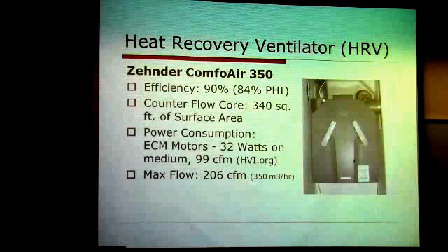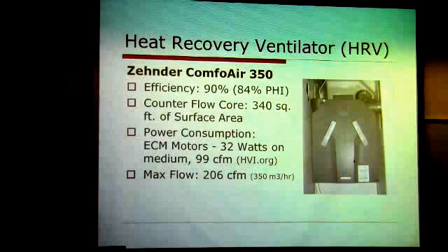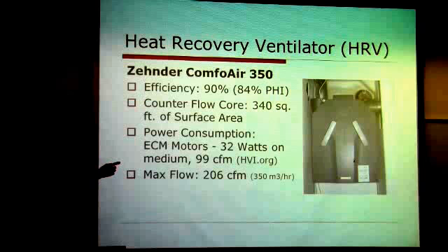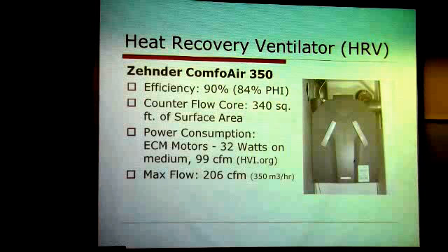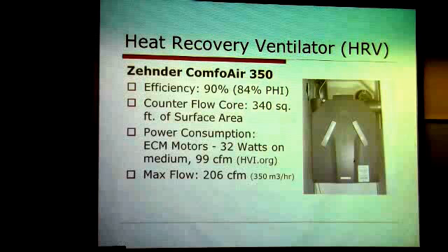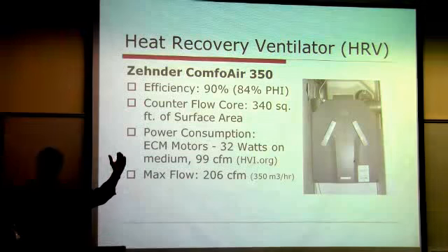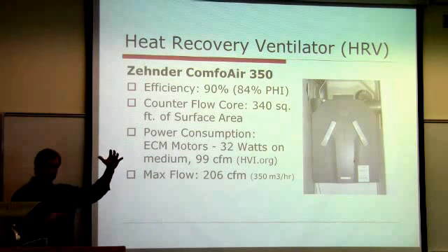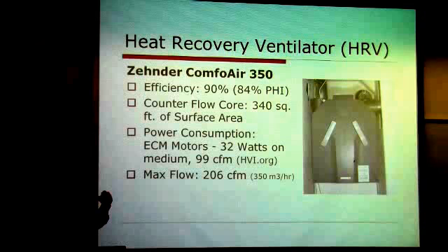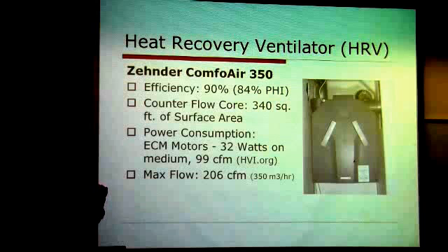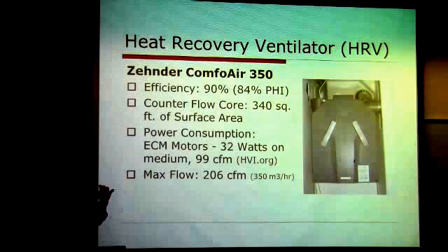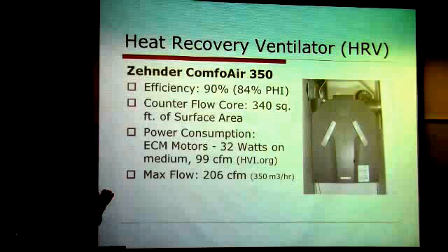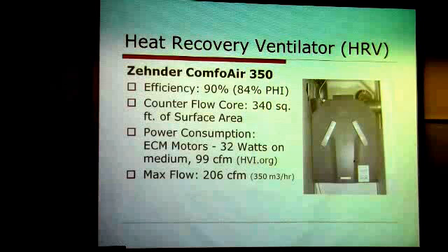But the only other way to cool it is provide a cooling coil downstream. So then you've got to watch for condensation. And if you use the earth to cool, the ground temperature around here might get up to 55 in the summer. So you can cool the incoming air from 95 probably down to 60, 62, just using a loop, not a refrigeration cycle, but just circulating glycol in a ground loop, at least 3 to 4 feet below the earth.